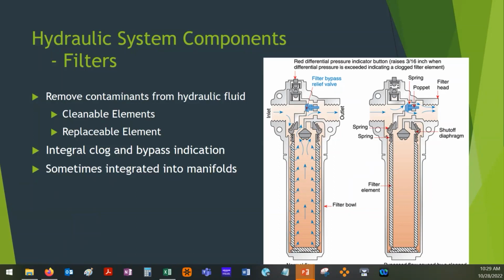And these had what they call a differential pressure button. So if the pressure got too high and pushes this poppet open, not only does it allow fluid to bypass, but that pressure also comes up here and pushes on this little item, and it causes a little button to pop out of the top or the side of the filter head. Typically it's red, some of them are purple.